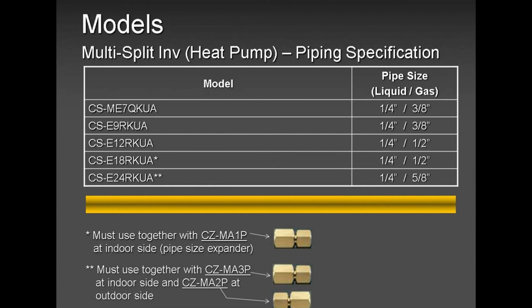This is just an example, for you to understand what it means when you buy an outdoor unit, let's say a 5 zone, a 4 zone, or a 2 zone, a 3 zone, and you just put 1 indoor unit. That's not enough. Even if you put 1 indoor unit and you cross the 4.5 kilowatts, it's still not going to work. It needs a minimum of 2 indoor units, as well as maintaining minimum and maximum capacity.